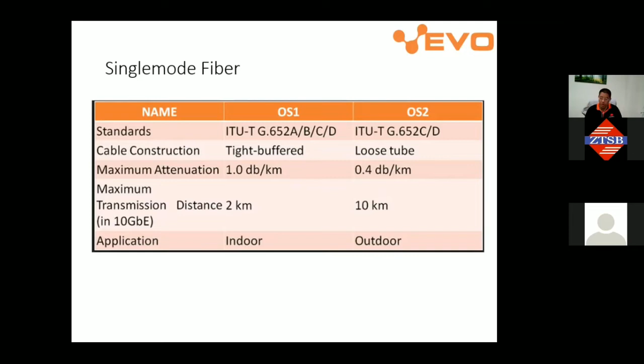You can see the loose tube and tight buffer types. For tight buffer, OS1 has 1 dB per km loss, and OS2 has 0.4 dB. The transmission distance is about 2 km to 10 km. That's why outdoor installations basically all use OS2. For your information, most fiber now, whether indoor or outdoor, uses OS2 fiber.